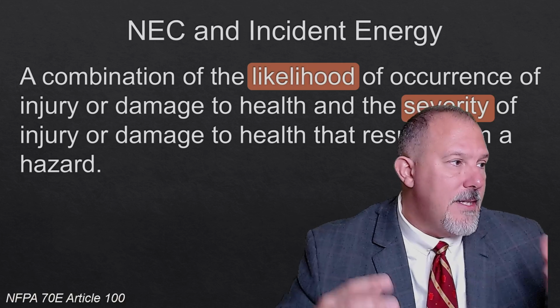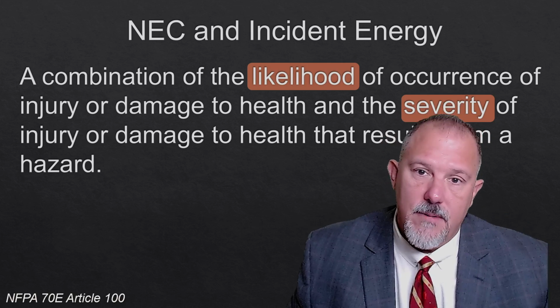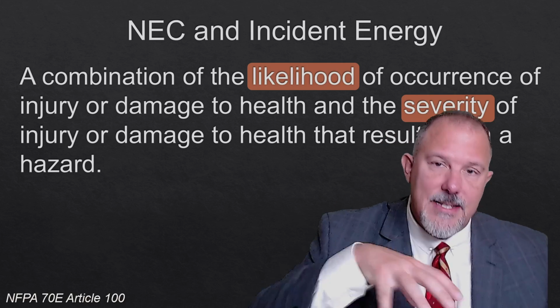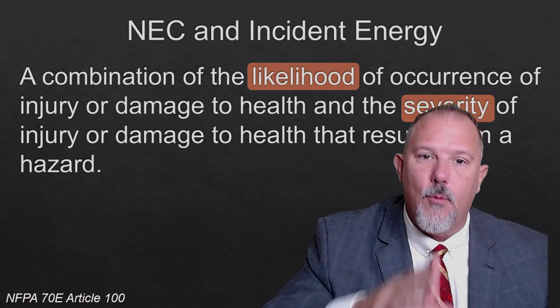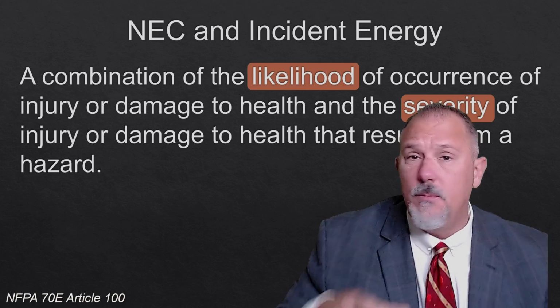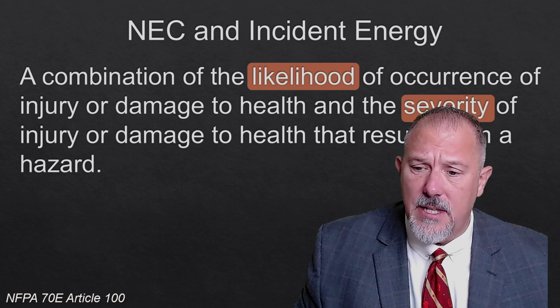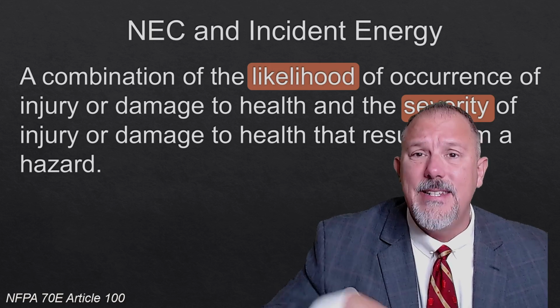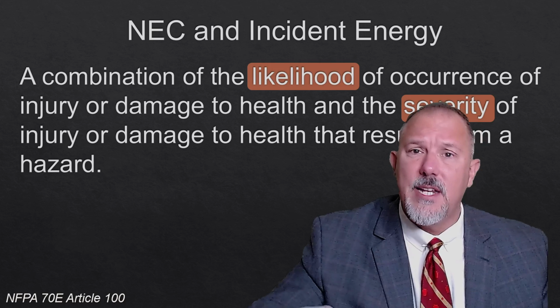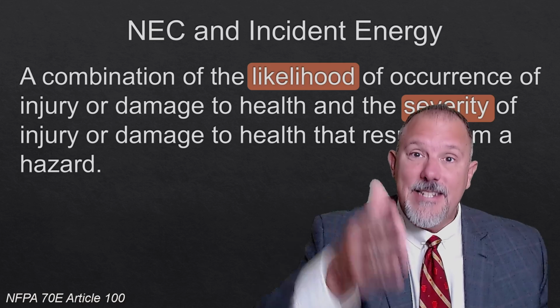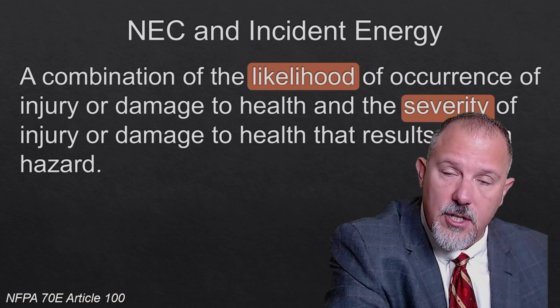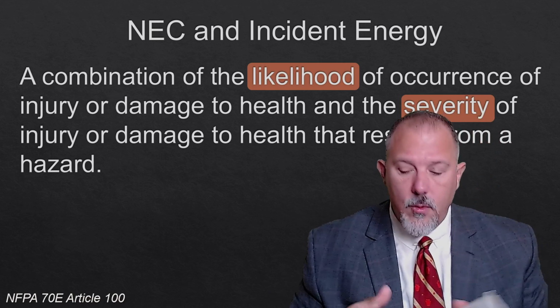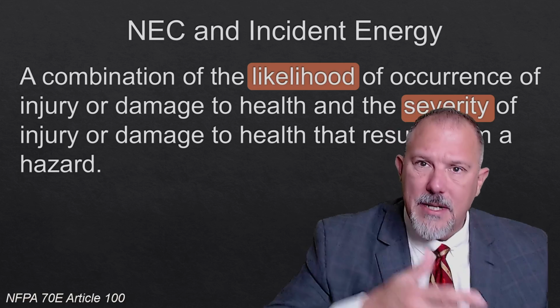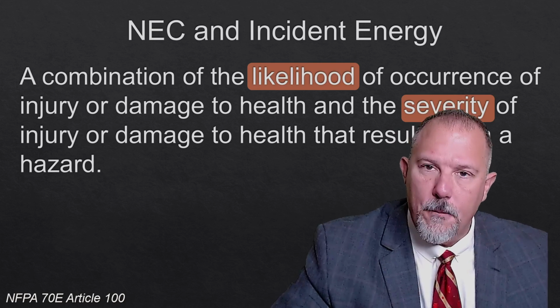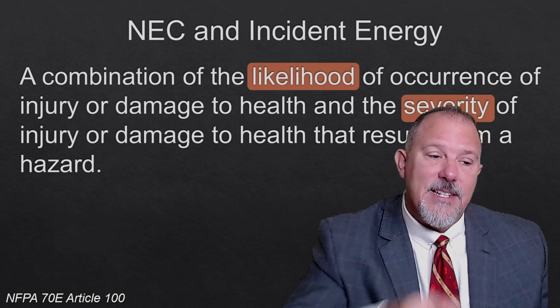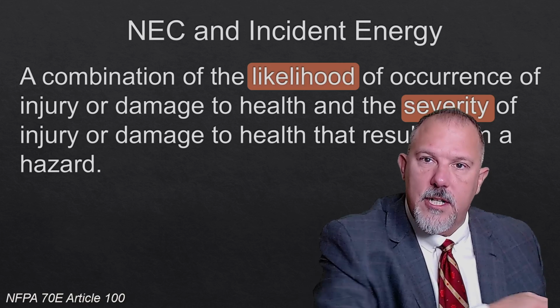So with the NEC and incident energy, I would say look at sections of the code and try to figure out where it reduces the likelihood and severity. And what I didn't put in here are all of the areas in the National Electrical Code where we require disconnects. What does a local disconnect on a motor help us do? Establish an electrically safe work condition. Any place where you have HVAC equipment, you put a disconnect in front of it. What does that help the electrical worker do? Establish an electrically safe work condition.